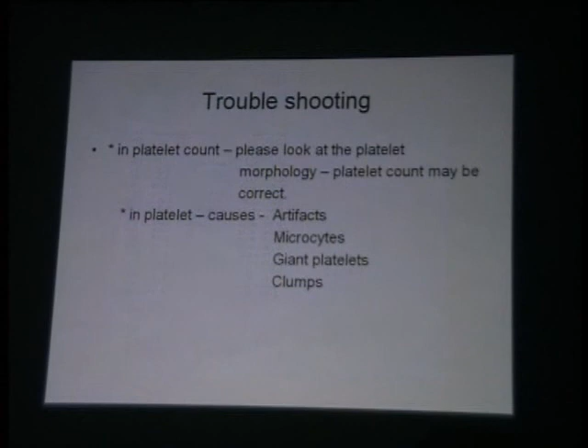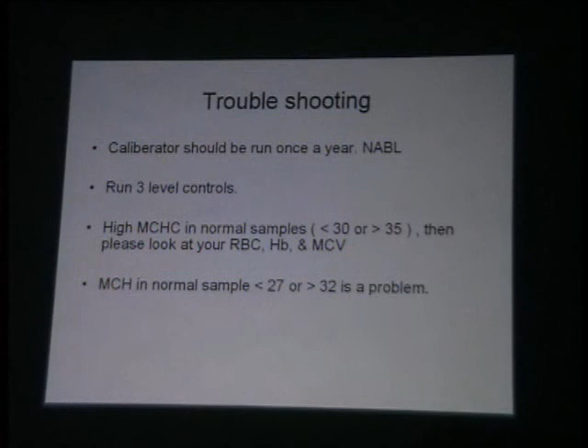I have had problems with my counters. In the morning I did a hemoglobin and it was giving me another reading. We normally have a habit of running one sample from the morning. The control may not change. But in the evening, it gave me a low hemoglobin value. And then I called the engineer. I said, how is it possible? Then they explained that the gain value of the hemoglobin lamp goes down sometimes.